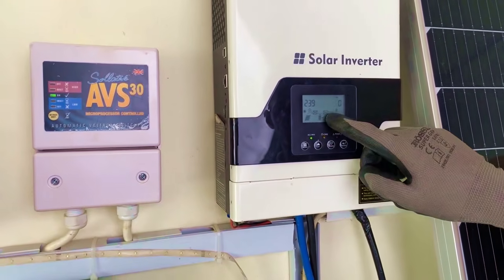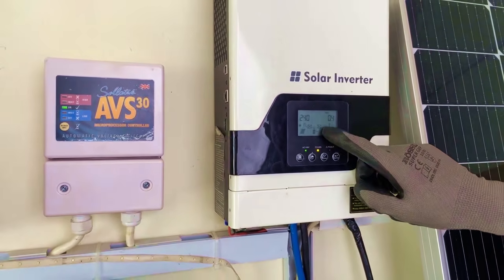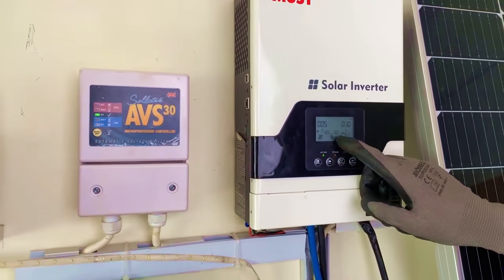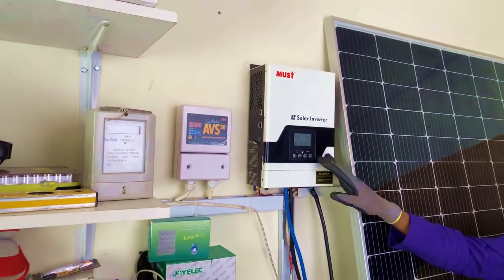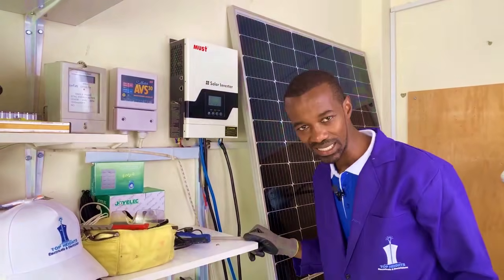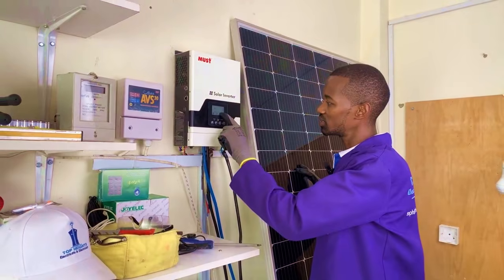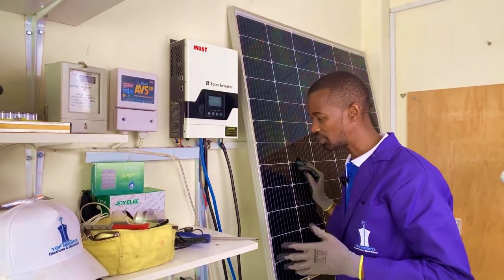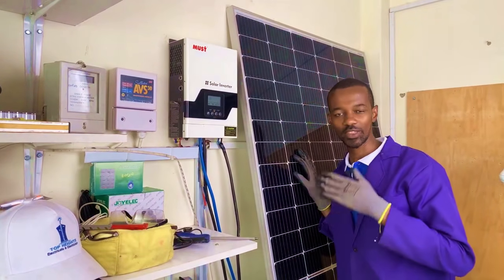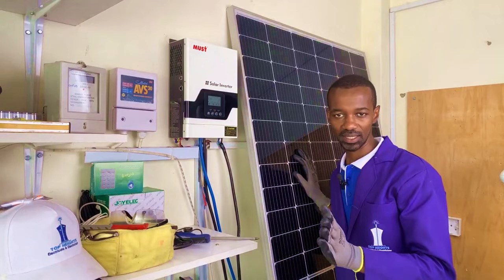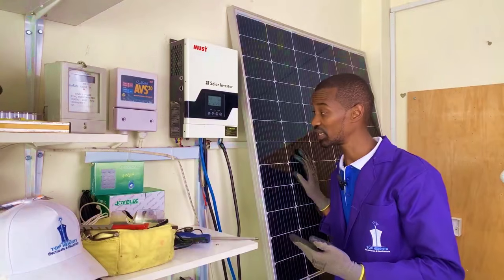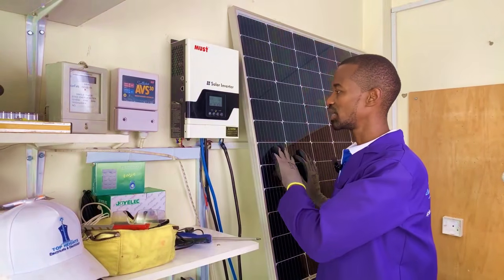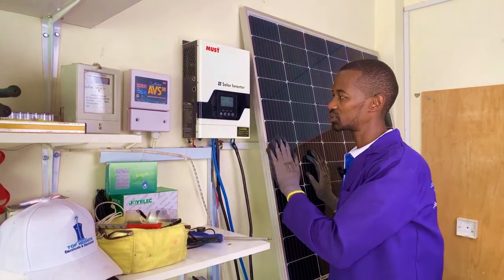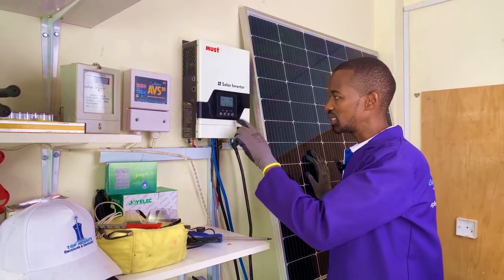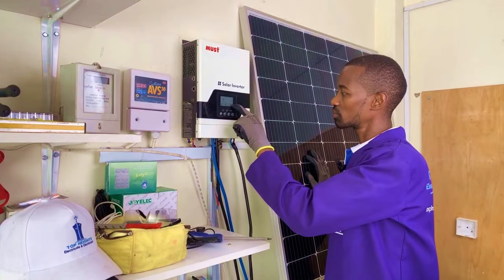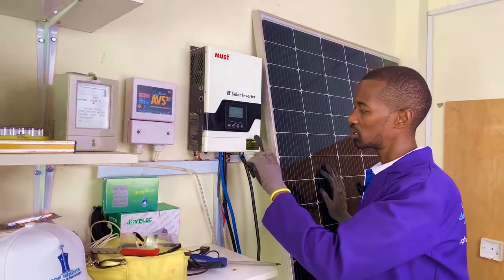But you can also see this box indicating AC being fed, and the other half of the box is DC, meaning after the conversion, because the primary purpose of an inverter is to convert DC to AC. So we have the incoming as AC, turned to DC because we need to charge the battery. The only way to charge a battery is if that power is converted from AC to DC, because the battery requires DC. On the solar side it is definitely DC, coming from the solar panels all the way to DC, which charges the battery. Interestingly, the incoming AC can directly supply the loads.